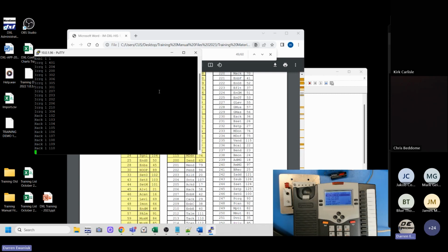When your PLC responds to it and acts on it, it sends the intercom system a handshake saying, okay, send me the next one, and the intercom system will send you the next one. You'll process it and send a handshake. So it's one at a time, but in control of your system as to when the next one goes out. It will queue up all of these station call requests ready to go out, and as you read and process them, it will send you the next one until it clears out the queue.